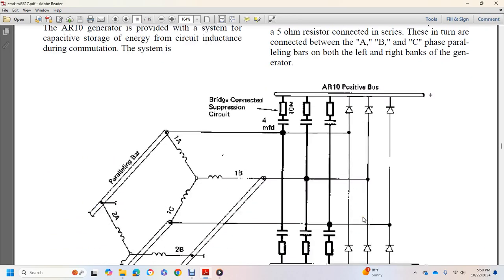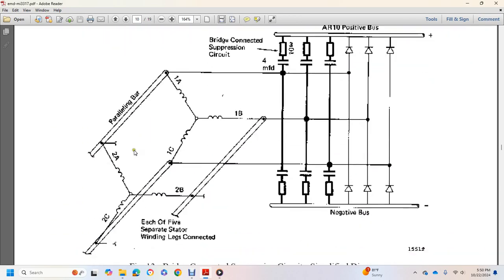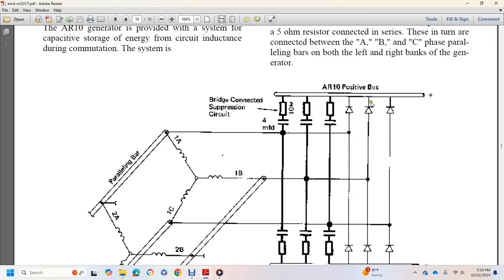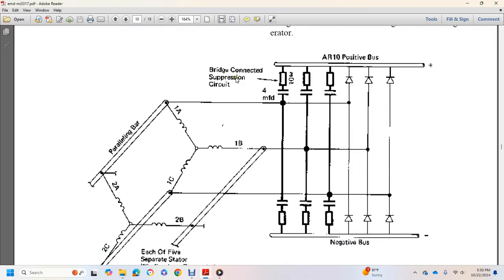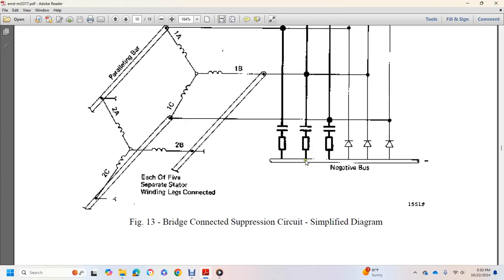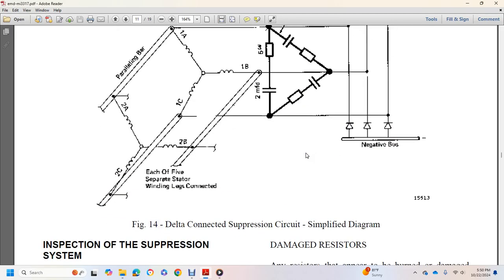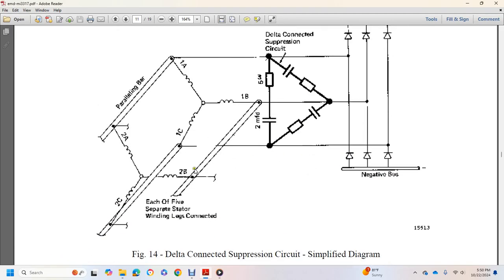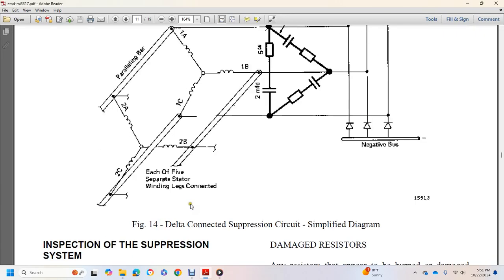banks of the generator. So we have a parallel bar, three-way winding, and it goes this way, and we have 2A, 2B, 1A, 1B, 1C, and then it goes into a positive bus. There are rectifier bridges over here, and bridge suppression circuits with capacitors and resistors. So once again, we see a delta connected suppression circuit through the parallel bars of the 3 windings of delta connected suppression kit, capacitor, resistor, diode, negative bus, and AR10 positive bus.